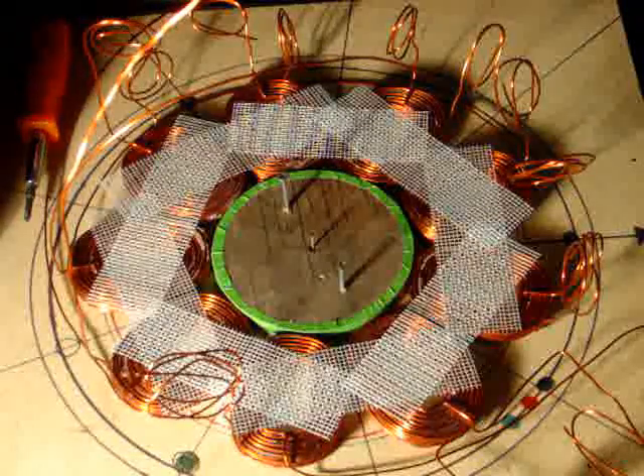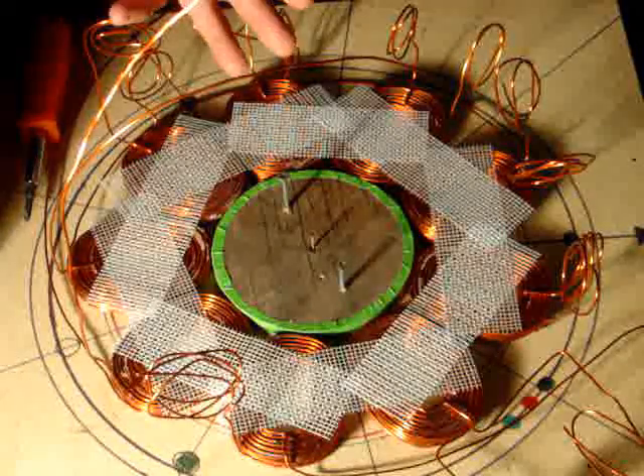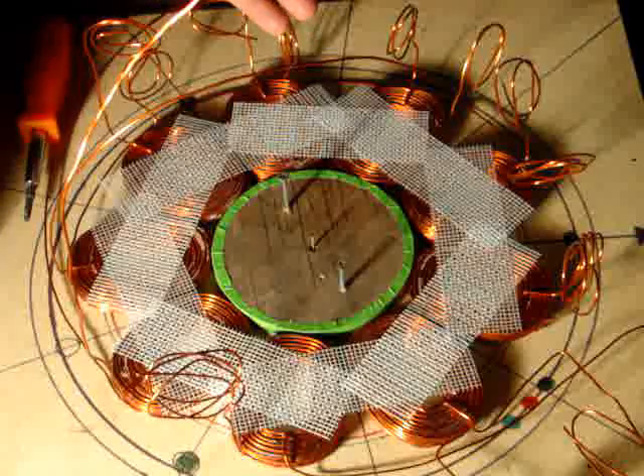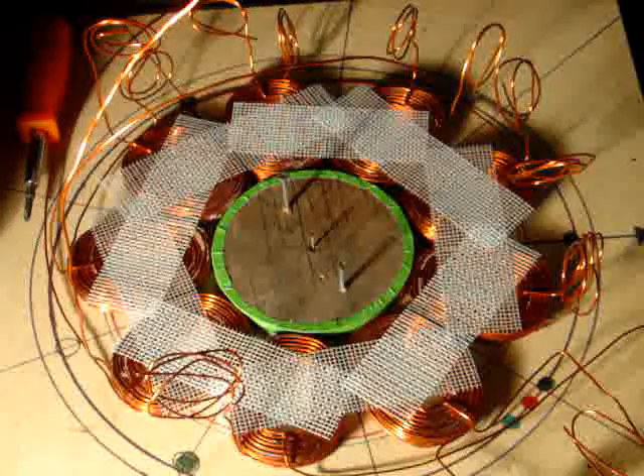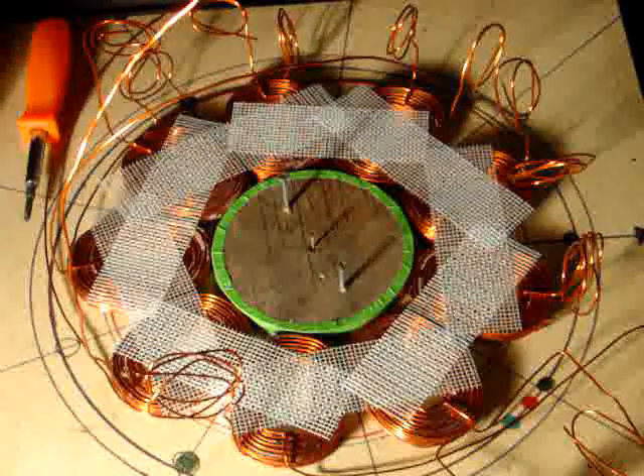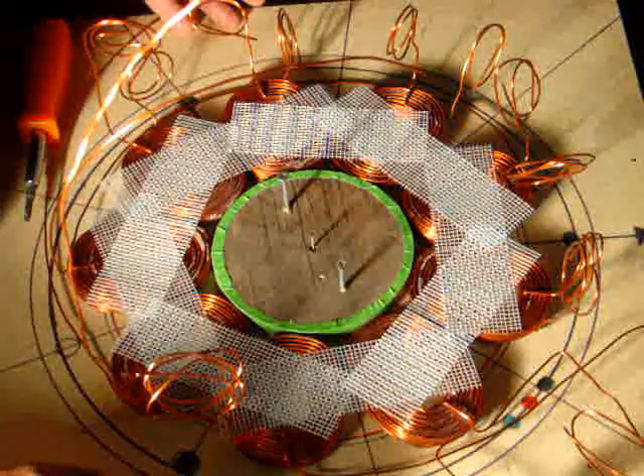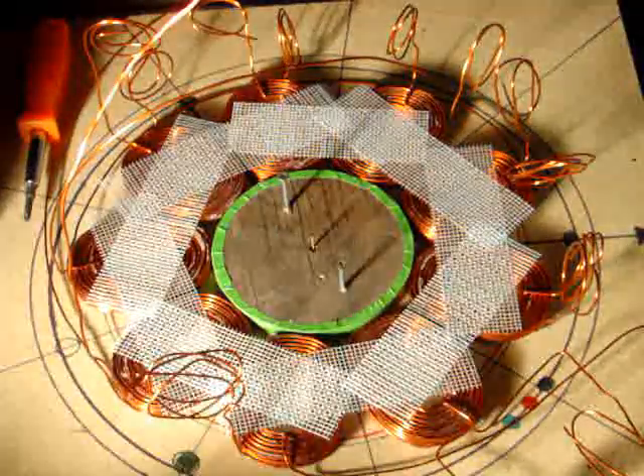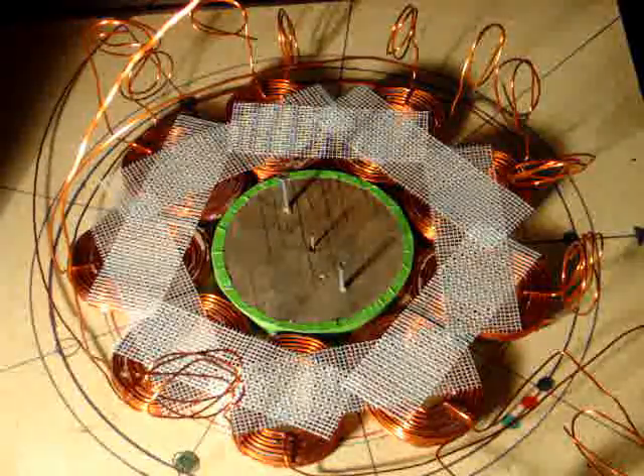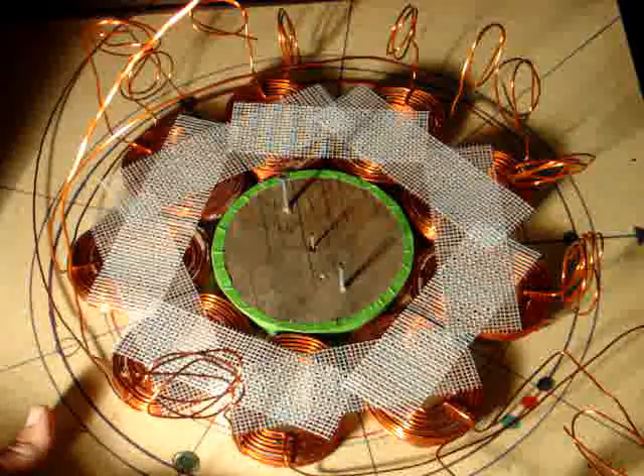Basically, to start off, delta is a lower voltage, about half voltage, and more amps. And then star is twice the voltage and half the amps. But that doesn't ring true all the way. Once the wind starts picking up and gets up to a higher level, the current will flow more in delta. Basically, you multiply your voltage times your current and you come up with a certain amount of power. You'll find out that in the higher winds you're going to get more power out of delta. But 90% of your wind and your power is basically going to come out in the low winds for low RPM. And that's going to be in star. That's why we wire this in star. We'll show you a diagram of that later.